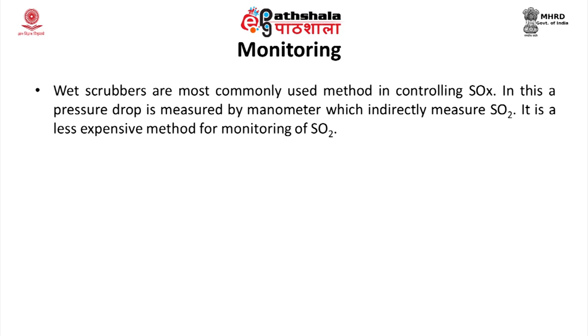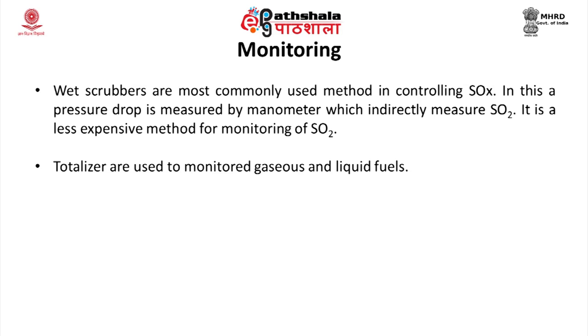The molecular weight of SO2 is double that of elemental sulfur. By monitoring the rate of fuel use, the emission of SO2 is calculated by assuming complete conversion of the fuel containing sulphur. Totalizers are used to monitor gaseous and liquid fuel. Another monitoring method is to establish a relationship between fuel use and steam production for a fuel.